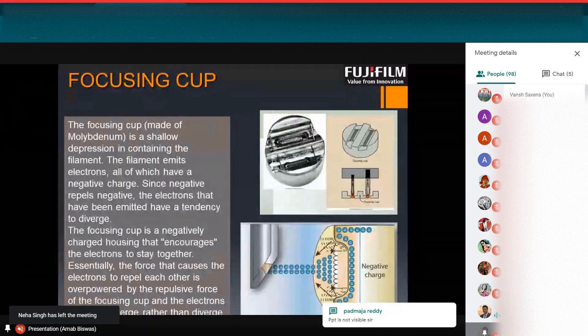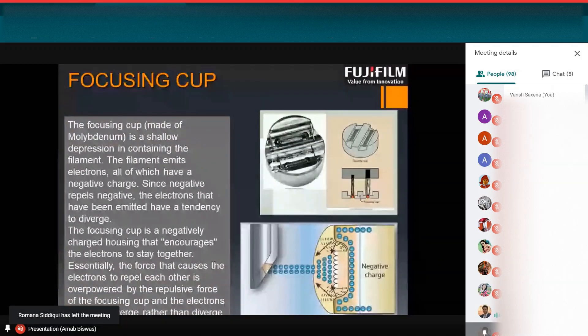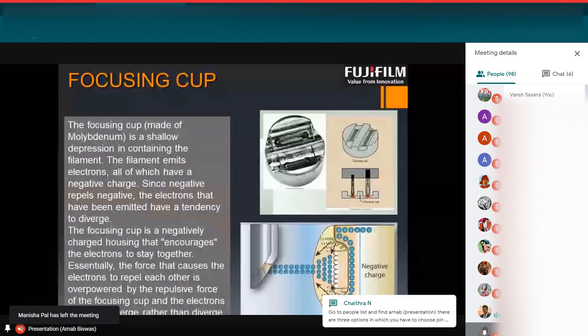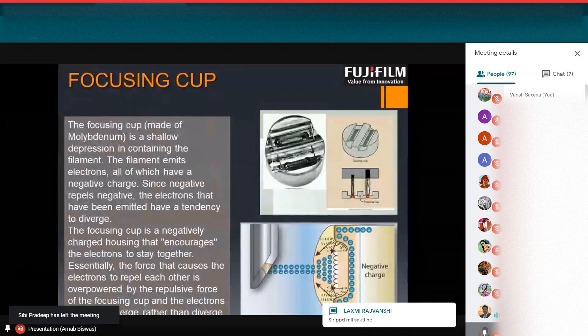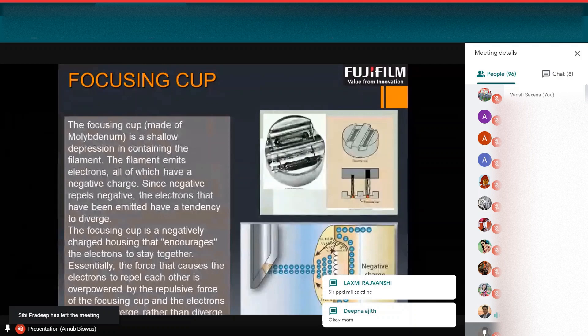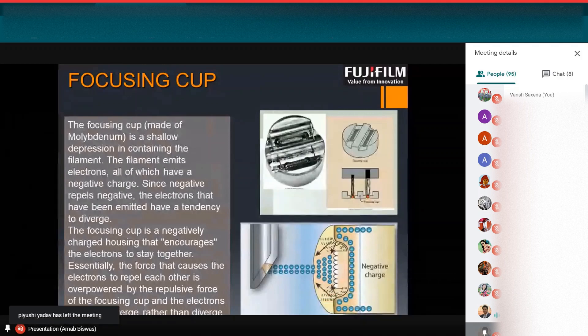So it has a negatively charged housing, which encourages the electrons to stay together. Essentially the force that causes the electrons to repel each other is overpowered by repulsive force of the focusing cup. And the electrons tend to converge rather than diverge. So we can maintain the flow in one direction. If we don't use the focusing cup, then the flow will be diverged in many directions.